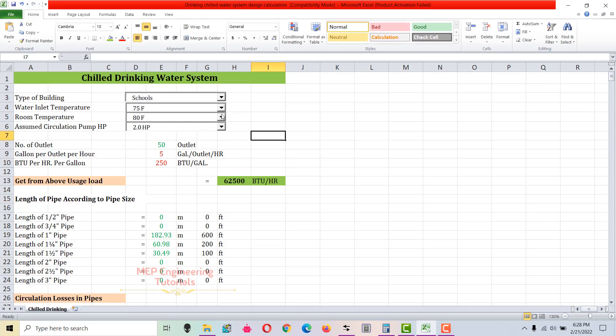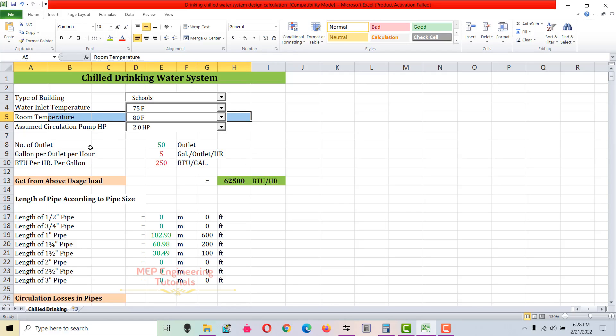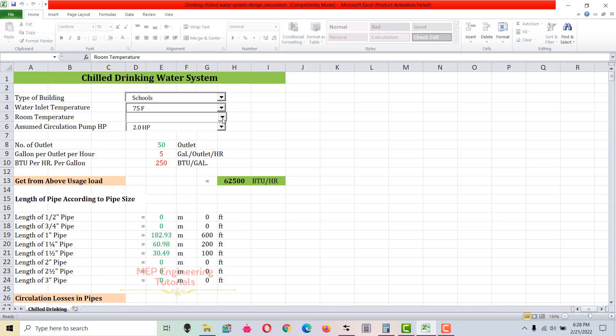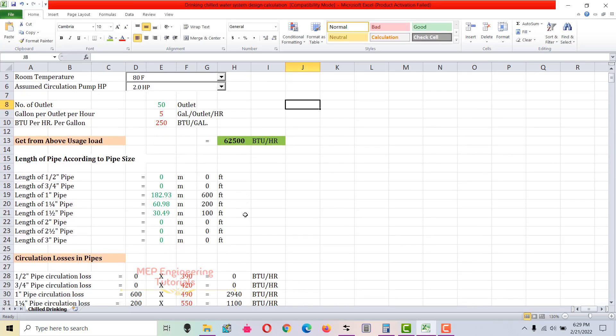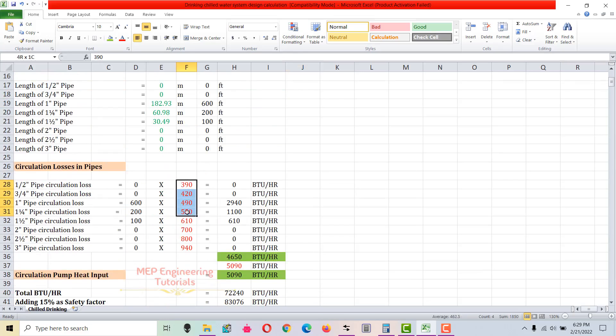The design chilled drinking water supply temperature is 45°F at the drinking fountain, and the water inlet temperature is 75°F. Next is the room temperature where we are going to place the fountains. There are three temperature options: 70, 80, and 90°F. Since we're normally placing fountains in corridor areas, I'm going to use 80°F as the room temperature.